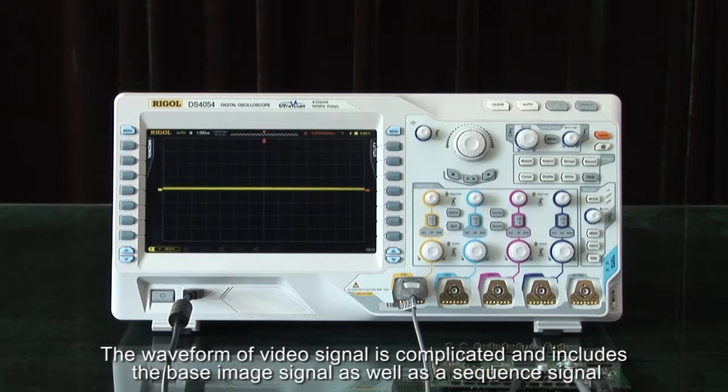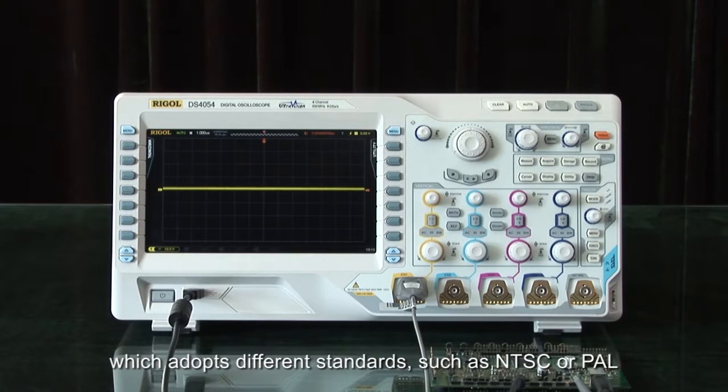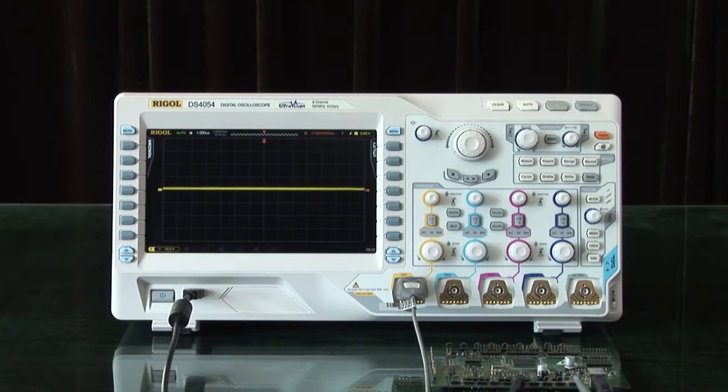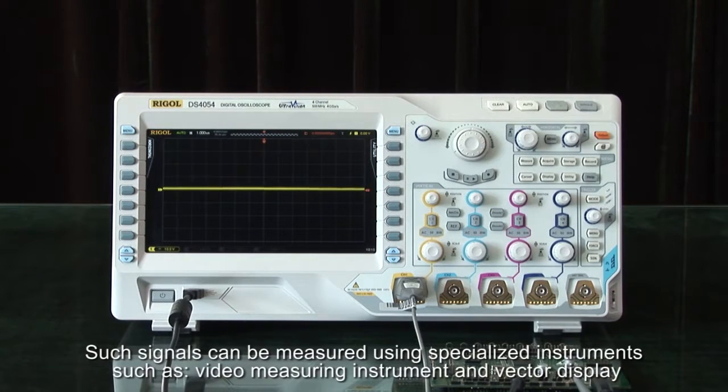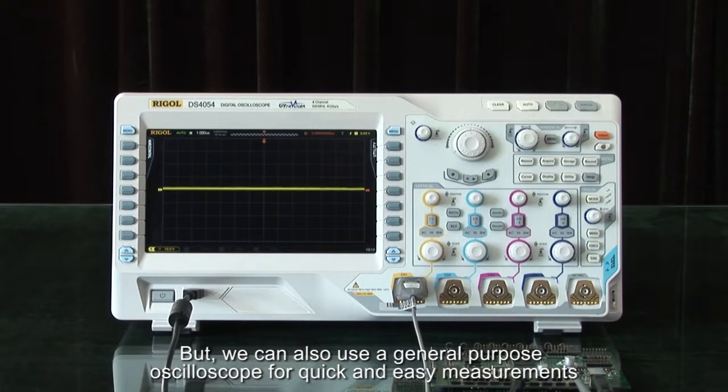The waveform of the video signal is complicated and includes the base image signal as well as the sequence signal which adopts different standards such as NTSC or PAL. Such signals can be measured using specialized instruments such as video measuring instruments or vector displays, but we can also use a general purpose oscilloscope for quick and easy measurements.